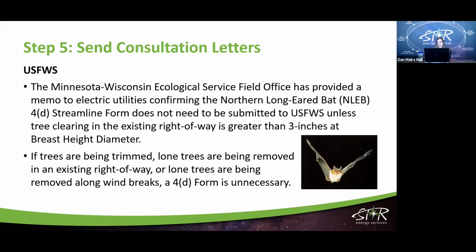U.S. Fish and Wildlife Service has a form called a 4D streamline form that you have to fill out for the northern long-eared bat always, but the Minnesota Wisconsin Ecological Service field office provided us with a memo, and a memo sent out to the electric utilities confirming that the northern long-eared bat 4D streamline form does not need to be submitted to U.S. Fish and Wildlife Service unless tree clearing in the existing right-of-way is greater than 3 inches at breast height diameter.